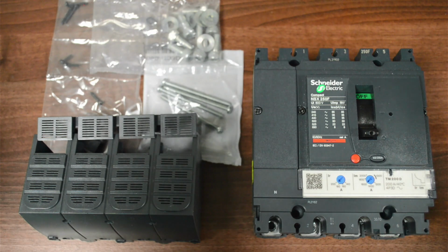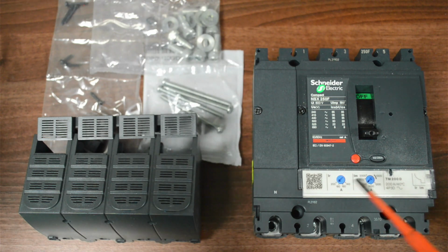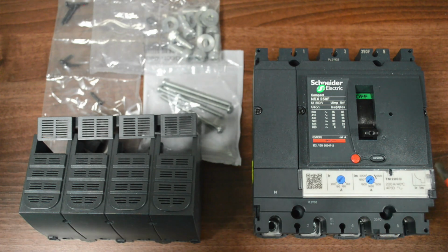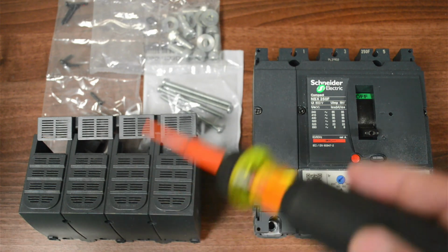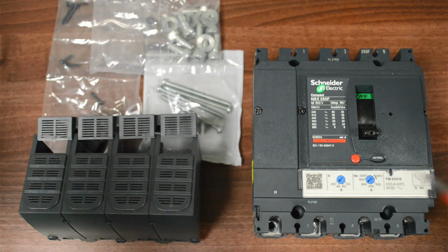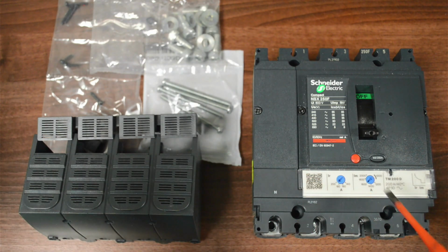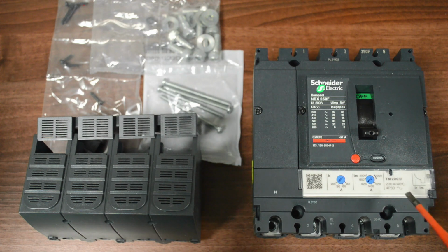You've got the tripping curves and characteristics in the wiring regs. With these, they are manufacturer specific. You'll have to refer to their literature for the maximum earth loop impedances and their short circuit ratings, and then actually setting them up as well. There is different ways for the different products of how you do it, and likewise again bolting them into the board. We'll have a little look at the instruction sheet for this because I've got one to hand, so we can talk about that as well.